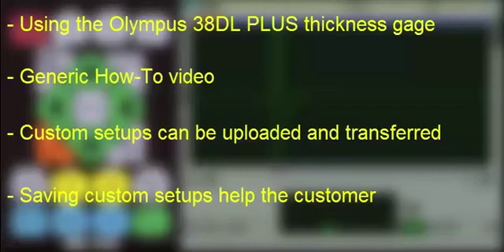After you solve a difficult application by making internal adjustments to the default transducer setup, you should save the setup. This way, the customer does not have to make these internal adjustments every time they want to use the instrument. Instead, they can simply recall the saved custom transducer setup.